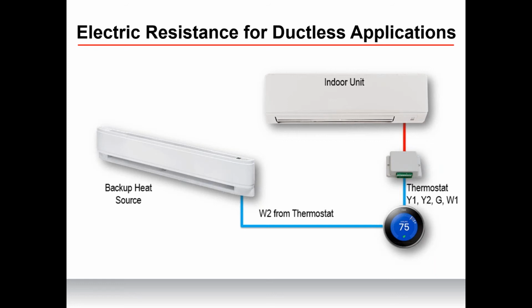Keep in mind that it's to Mitsubishi Electric, so other heat pump manufacturers may or may not have this capability. I can't speak to that. I can just speak to what Mitsubishi Electric can do. It's as simple as utilizing a third-party thermostat and our thermostat interface, and wiring in that backup heat source to W2 with the thermostat. So essentially you have first stage heat pump, second stage backup electric heat source. So it's very, very easy to integrate that. We have some different methods we'll look at as well, but this is about as simplistic as it gets.